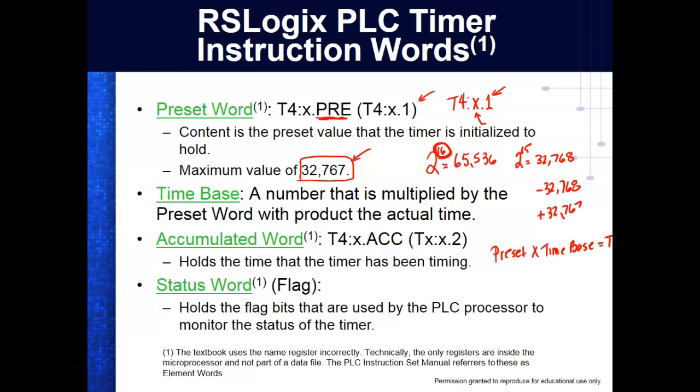So our constant would be like pi, right? Square root of 2 would always be what? So you can't change the square root of 2. Square root of 2 is square root of 2, right? But in programming, a constant means I actually literally have to change the actual program itself. So time bases, we can't address the time base. Once I select the time base, then that is the time base, right? And how would I change the time base? I'd have to go offline. I'd have to change to a different time base, and then I'd have to download it again, right?